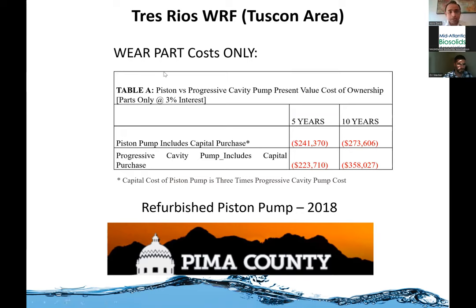But if we do a 5-year life cycle cost analysis or a 10-year life cycle cost analysis, the cost of ownership for the piston pump is very close to the PC pump, even if we consider that the capital cost is 3 times. So the cost of ownership is like $241,000 to $223,000, very close. But when we get into the 10-year life cycle cost analysis, present value, the cost of ownership of the piston pump is lower than the PC pump.